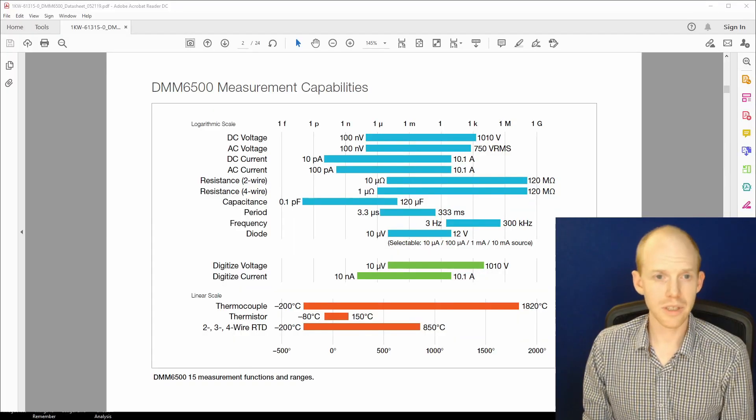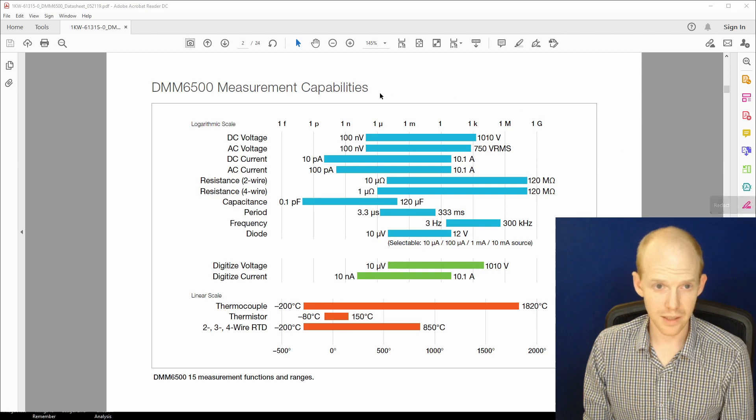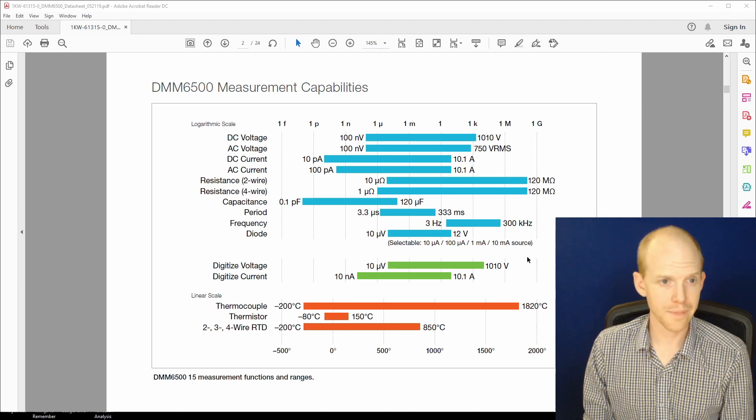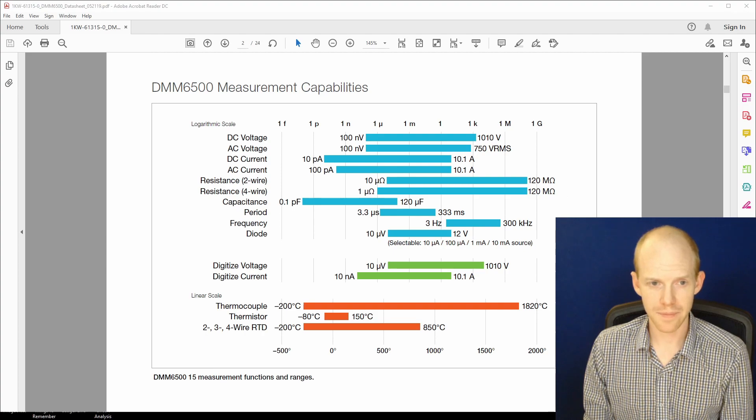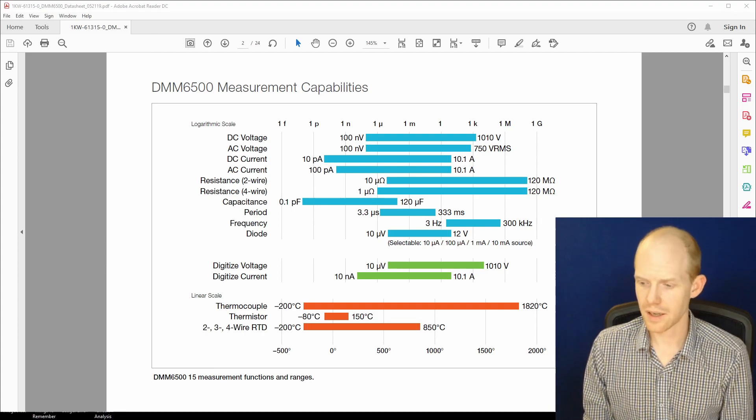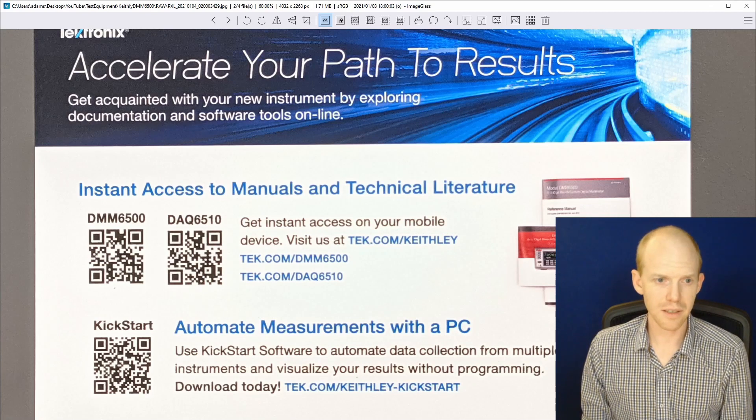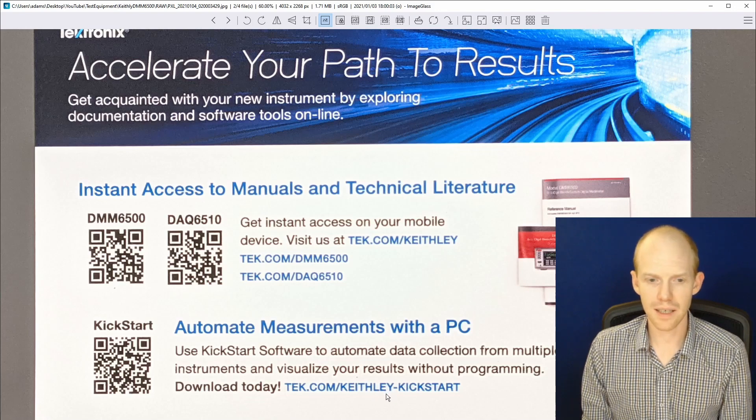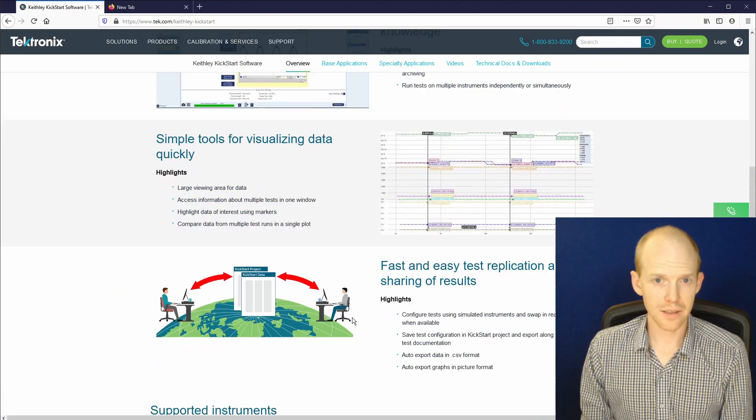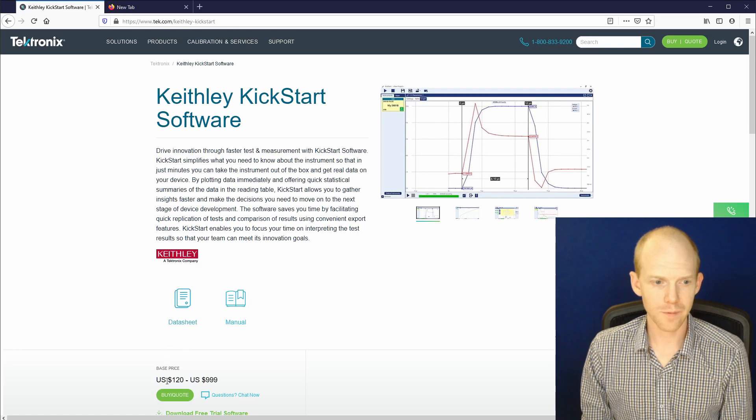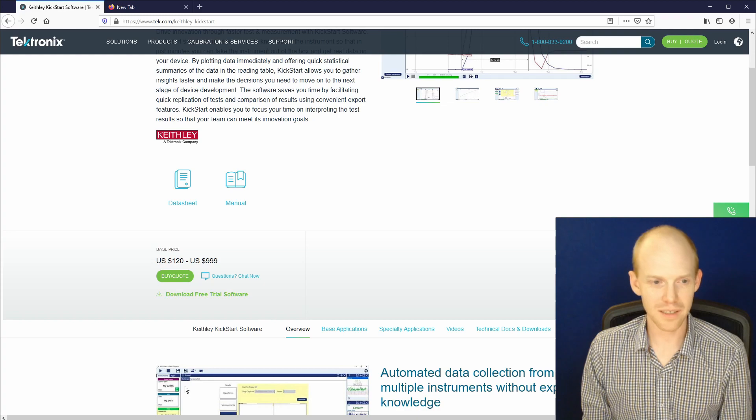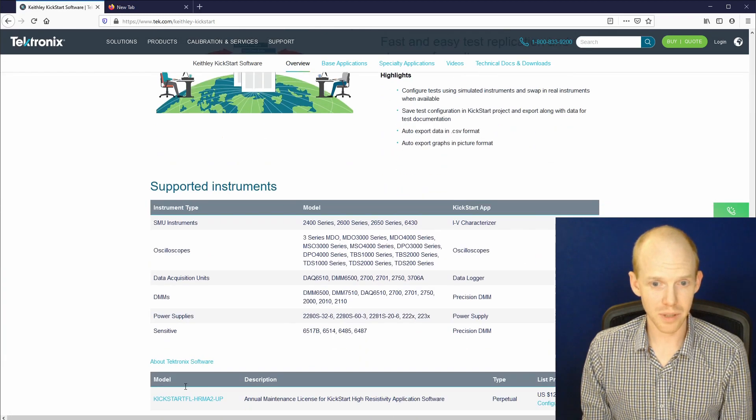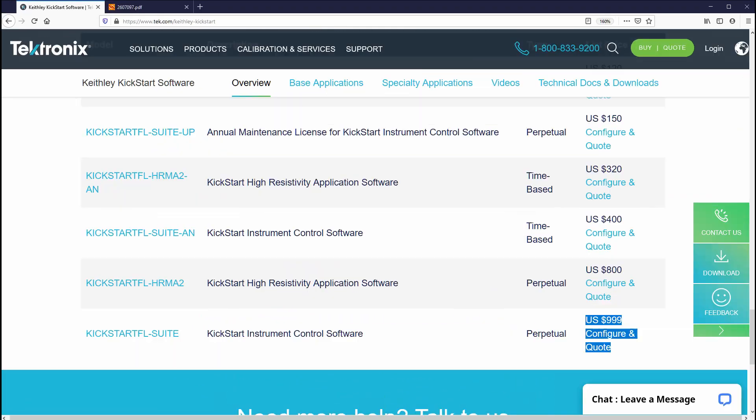We're back at the computer here, so let's check out a couple of the specs. Here's the data sheet. We got DC voltage in the nanovolts to kilovolts, and we got current in the picoamps to 10 amps. Here's a picture that was on the top of it. So it says to get started, go to tek.com/keithley-kickstart. That brings us over to here. It looks like a free trial of this software that makes it so you don't have to learn how to program. All you have to learn how to do is pay $999. I think we better check out some Python here.